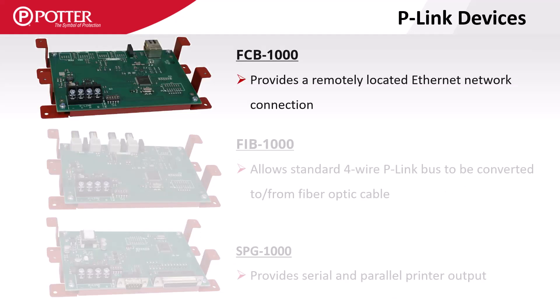The FCB-1000 provides a remote Ethernet connection for IP reporting only, allowing the Ethernet port to be located as close to the source of Internet access as possible. The FIB-1000 converts the P-Link communication to and from multi-mode fiber optic cable and is installed in pairs — one will act as a transmitter and the other a receiver.